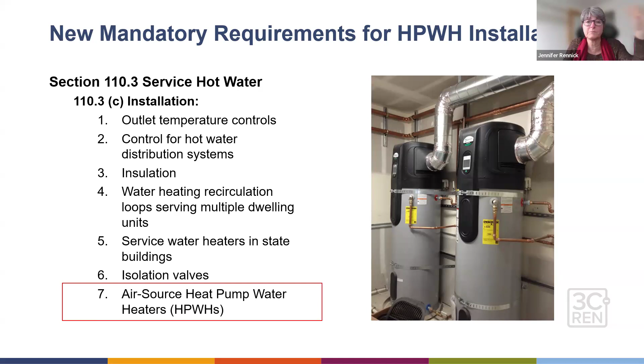So this is probably one of the biggest sections of change in this part of the code. Again, I pulled the language from the code for you so you could have it as a reference. But one of the things they're now stating overtly is that if you have an air source heat pump water heater, you have to have a backup heat source. That's because a lot of the compressors cut off at temperatures that are really not that cold. Some of the units will stop working in heat pump water heater mode at only 45 degrees Fahrenheit. The newer ones will cut out at 37 degrees Fahrenheit.